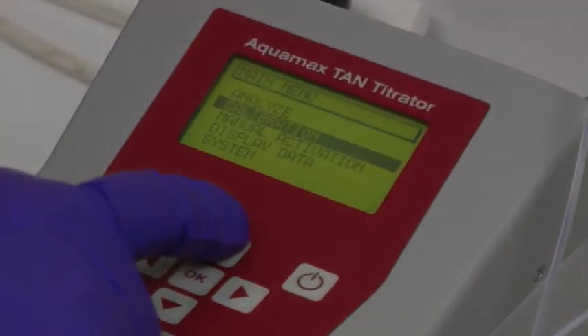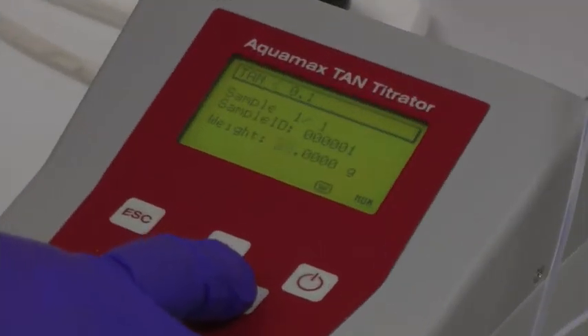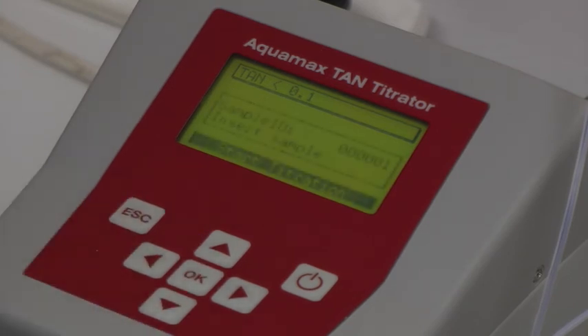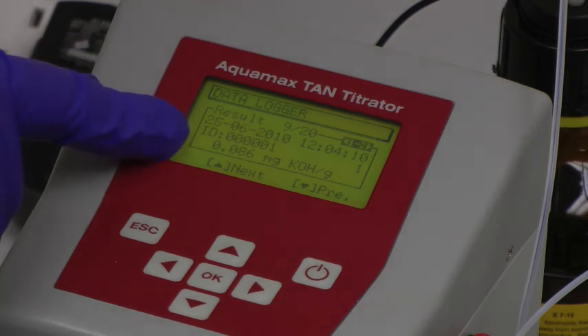From the main menu, Analyze is then selected. If the approximate TAN value is known, it can be selected on the next screen. The weight of the sample is entered through the keypad, and the titration process itself can be started after the pH 11 standard solution has been removed and replaced with the oil sample. Once the titration process is complete, the result is displayed as a milligrams of potassium hydroxide per gram reading.